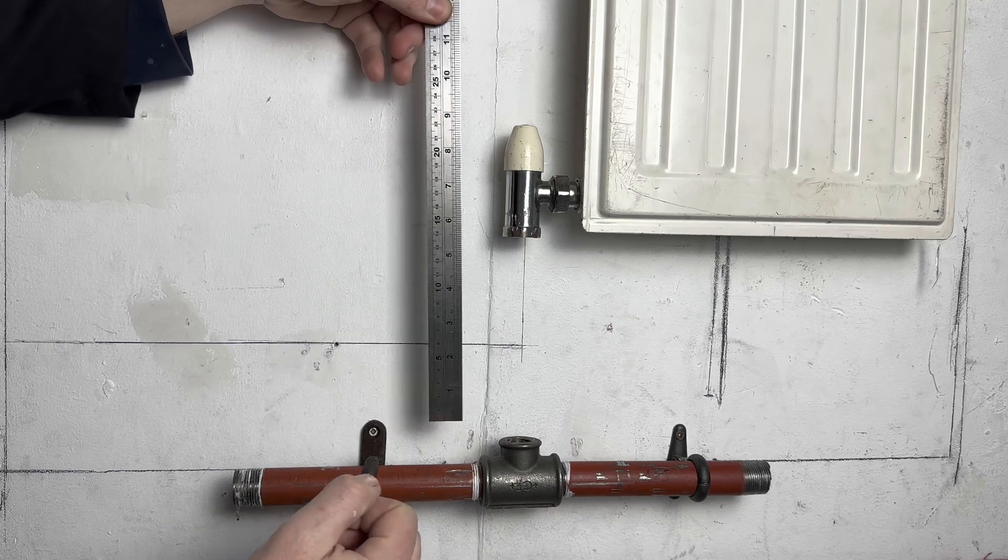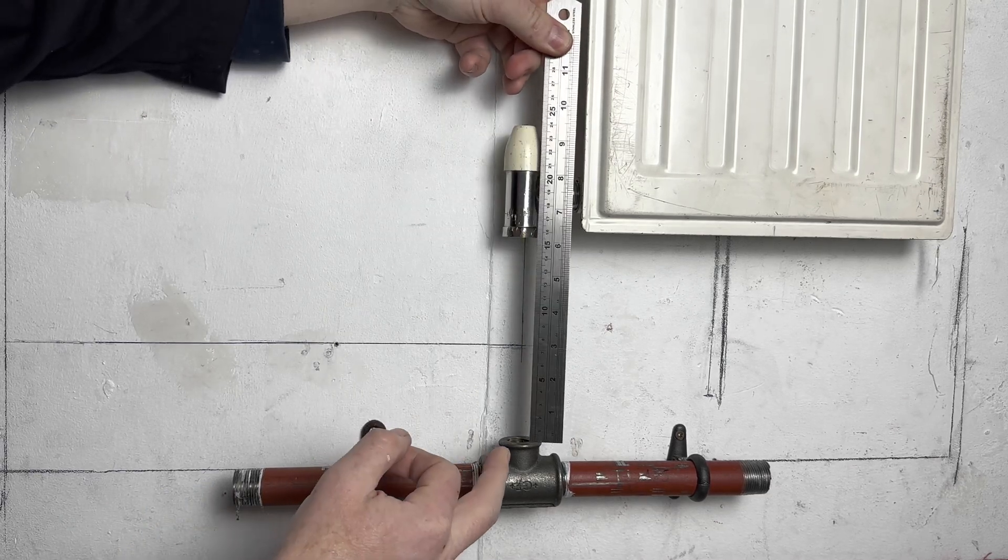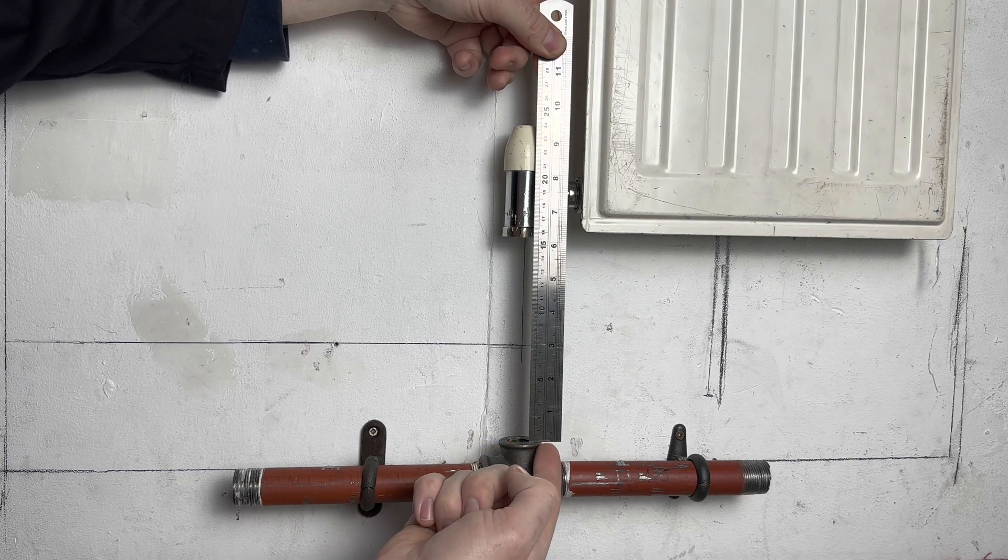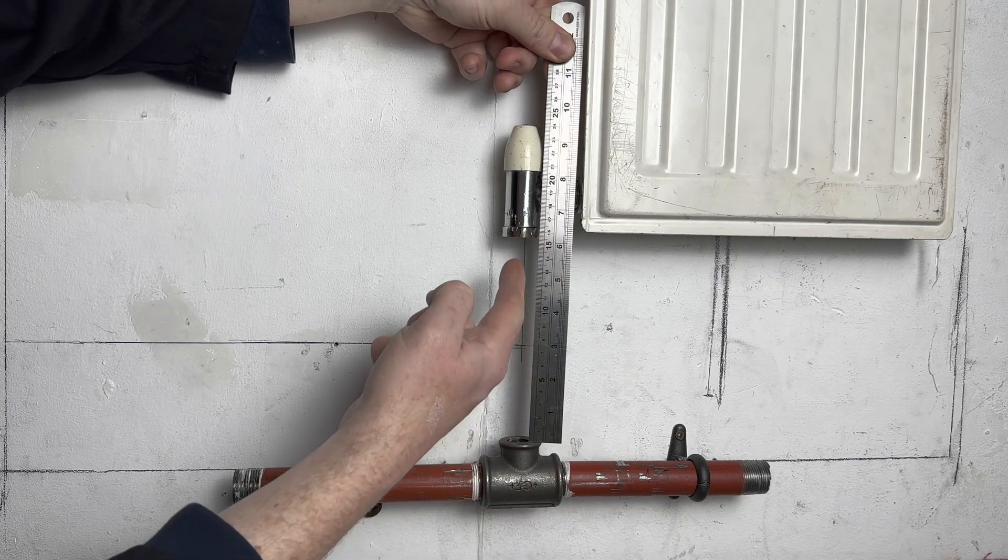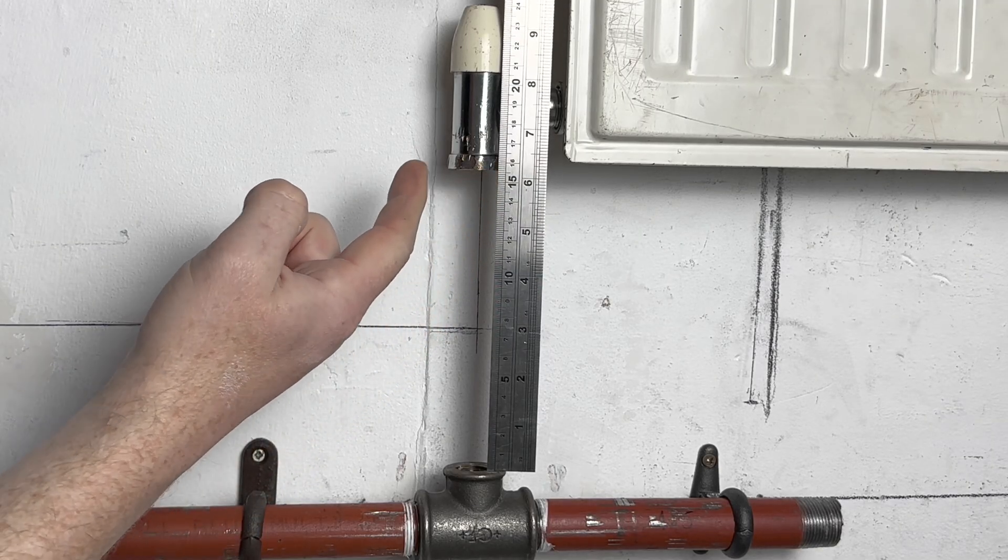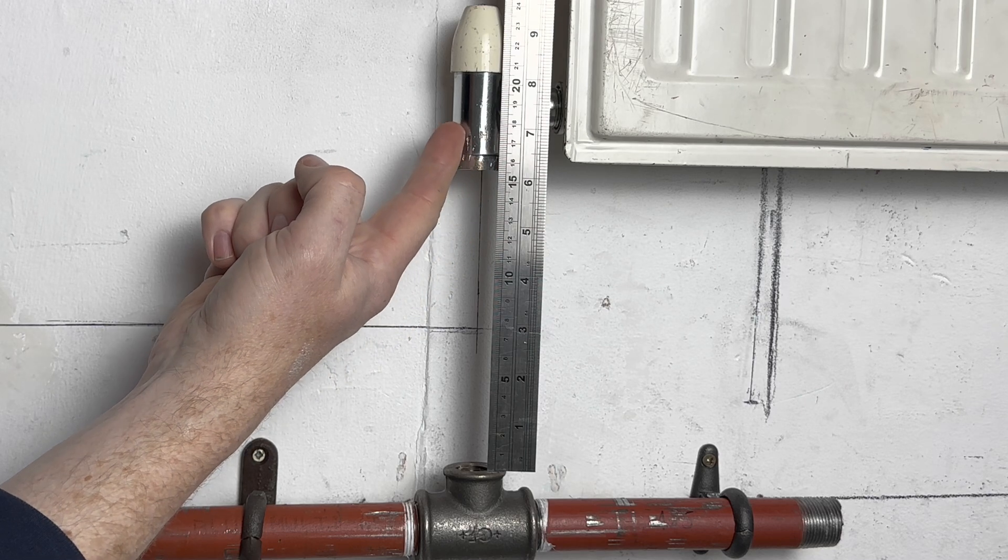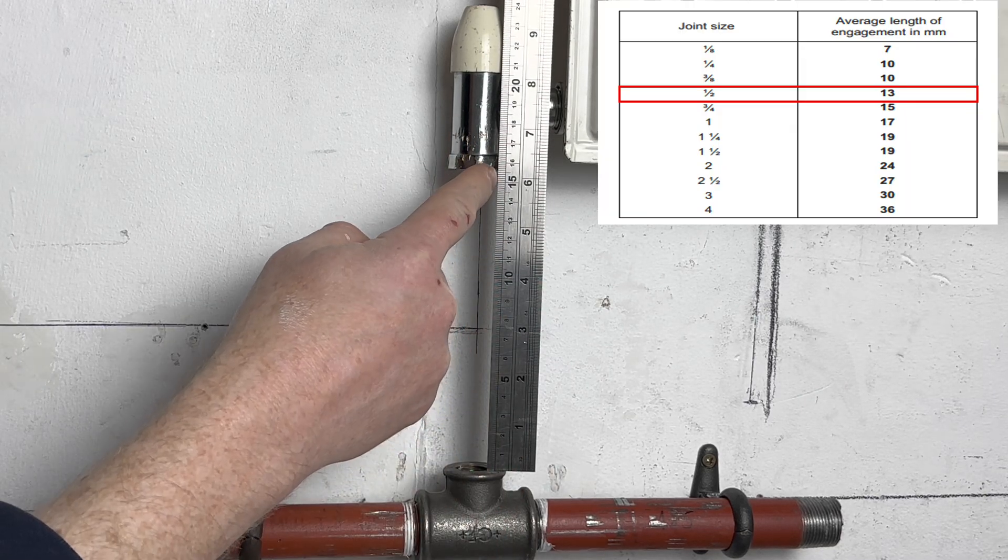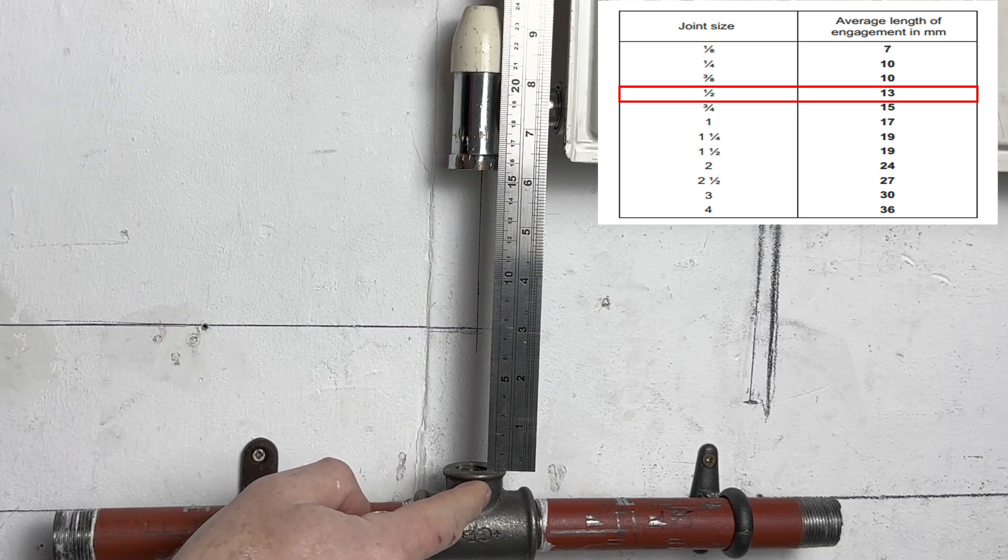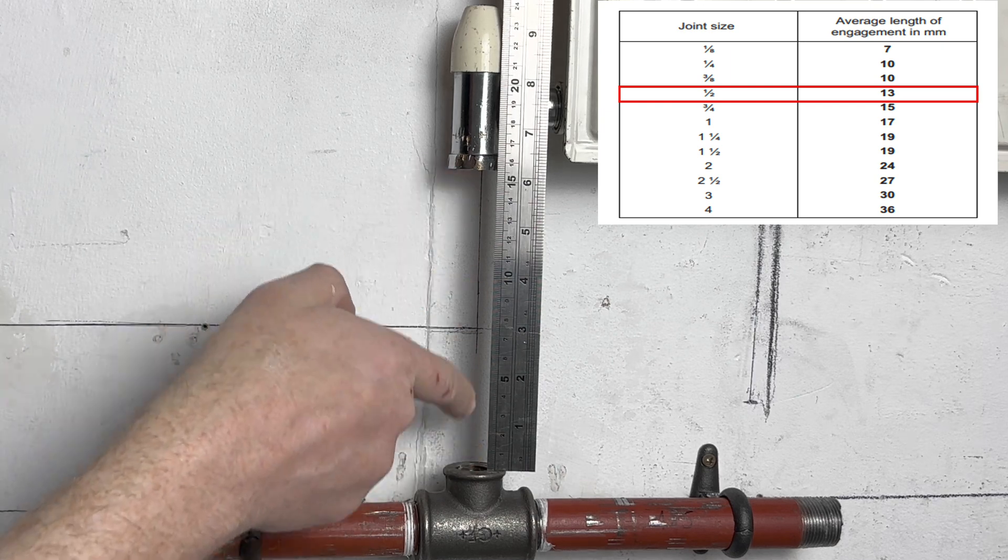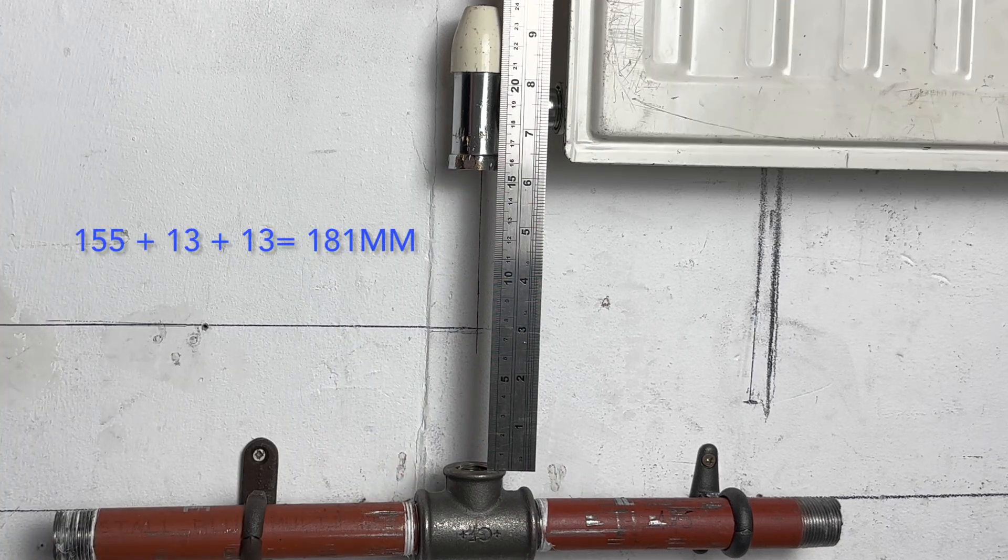Another way to work out the pipe size without using the Z dimension, measure from the end of the fitting to the end of the fitting, which is 155mm. As we know that the pipe is inserted 13mm into each fitting, so 155mm plus 13mm plus 13mm will give us 181mm.